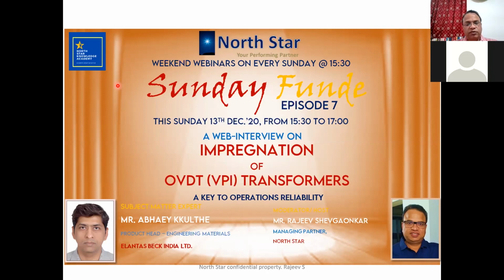The key is how you are protecting the insulation and how you are controlling the degradation of the insulation. That can be done very easily by monitoring the temperature and load on the transformer and the moisture ingress in the transformer. If you take care of these factors, it is quite possible that the transformer will serve you over a long period of time.